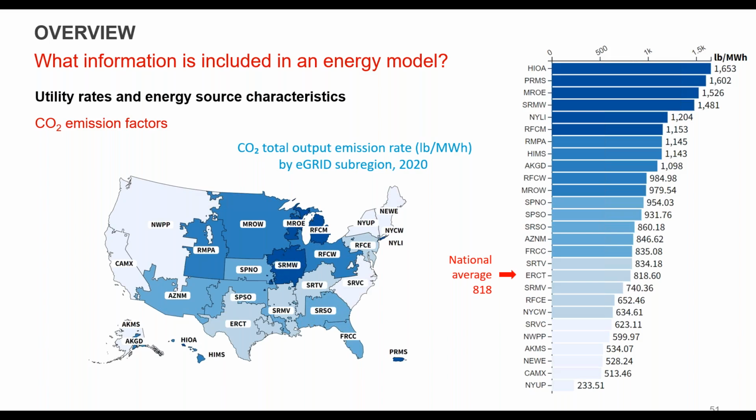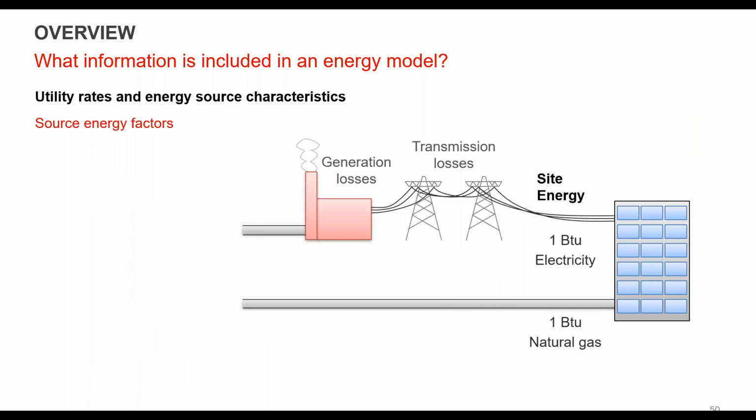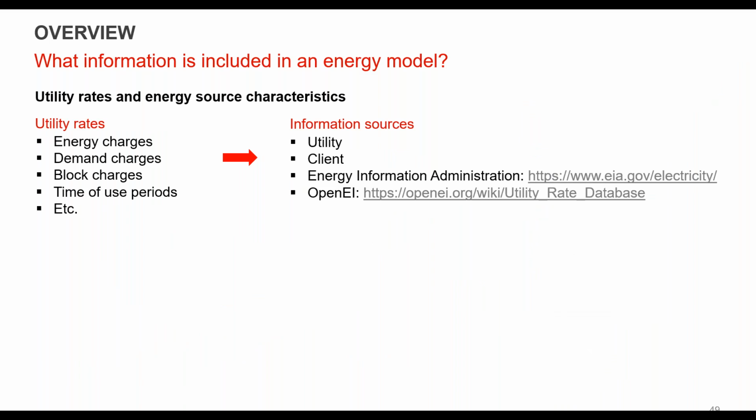A couple of questions here. Somebody asked about block rate, so we'll go back to that. I don't think I have a graphic for it, but block charges could mean that you are charged for every incremental block of energy you're using. It could be that for the first 500 therms you're paying 20 cents a therm, or some bundled rate, and then you get to the next 500 and the price might change. You might be paying 25 cents.